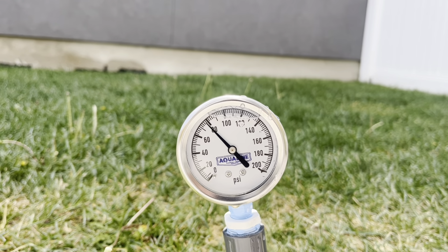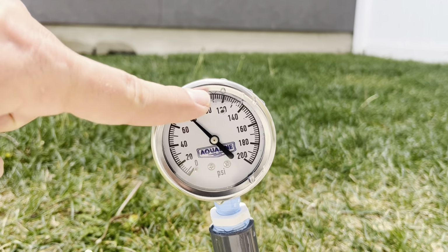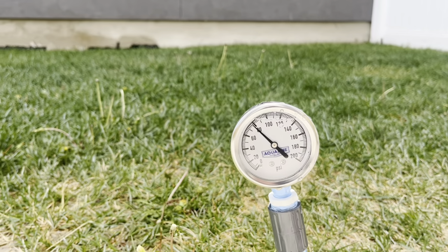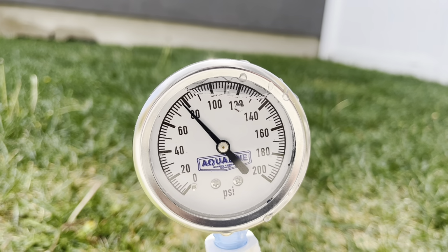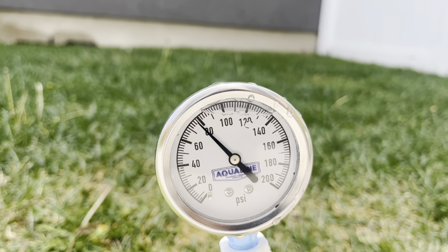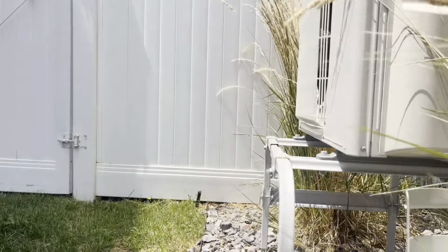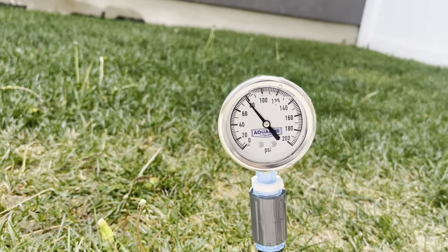So let's open up some nozzles and see what changes now. Remember, this is static pressure because nothing is going out. And so it's just sitting there, close to 80, 78, 79-ish. And that's because almost no water is going out. Because these are spurting out just a little bit, this isn't technically true static pressure, but it's as close as we're gonna get today.